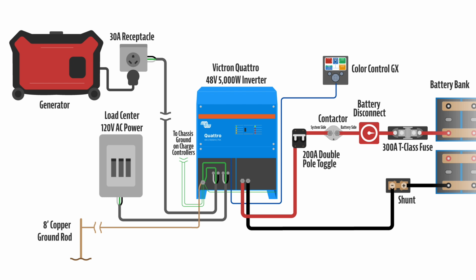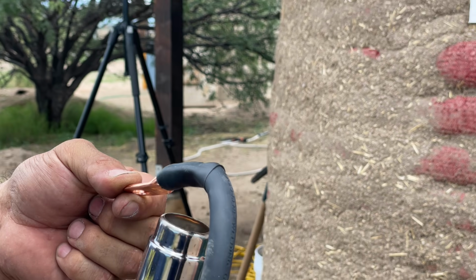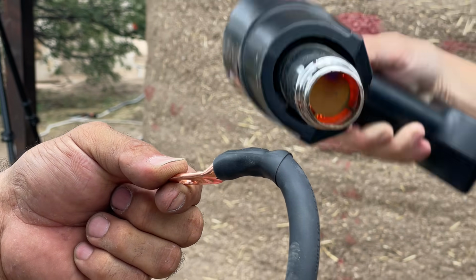If you haven't already, make sure that you have power running into your inverter. This is very simple—you're just going to run a big 2-aught welding cable from the system side of your contactor into the positive end, and then from the negative side of your shunt to the negative end. Our 2-aught wiring is based on our system size, how many amps and watts we're pushing through; you may need to go bigger or smaller depending on your setup.